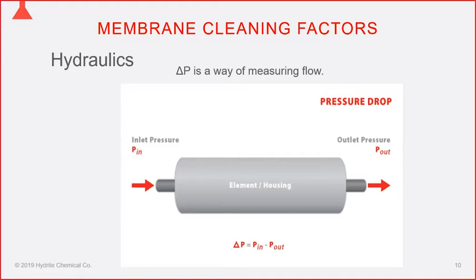The two most common things that cause problems in membranes: hydraulics getting out of whack — a sensor failure or a pump running wrong — or somebody misusing chemicals. How many times have account managers gone into a plant and been told 'your chemicals aren't working,' only to find something mechanical is wrong with the hydraulics? That's probably nine times out of ten. Calculate the pressure drop per stage: take loop pressure minus baseline pressure, divide by number of membranes per housing; you should get 10 to 15 psi.